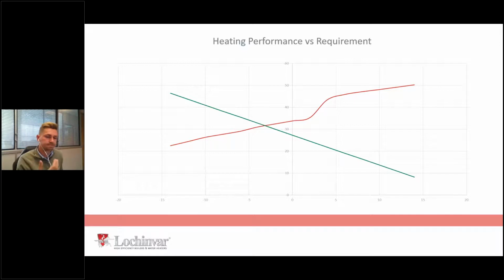And then if we go slightly more rural, into Norfolk or East Anglia, some areas of that, these big flat expanses, quite rural in some locations, you're probably looking more like -4, -5. Well, this green curve is basically a performance curve required to maintain a 350 meter squared office at a temperature of 20 degrees centigrade. And this heat pump is capable of doing that down to -3. So in a rural environment, the heat pump might be ever so slightly underspec. In a nice urban environment, this heat pump might be specified quite nicely actually, because -2 was the target, and this is incredibly close because it can work right down to -3 and still maintain that building at our desired set point.